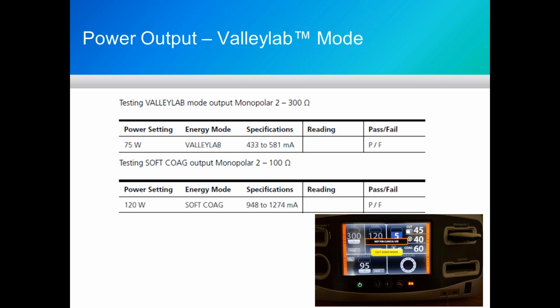And when you go into Valleylab mode, the display gets a little different on you. But again, we're going to test at a power setting, 75 watts. We're going to look for output current anywhere from 433 to 581 milliamps to determine whether that is acceptable or not.